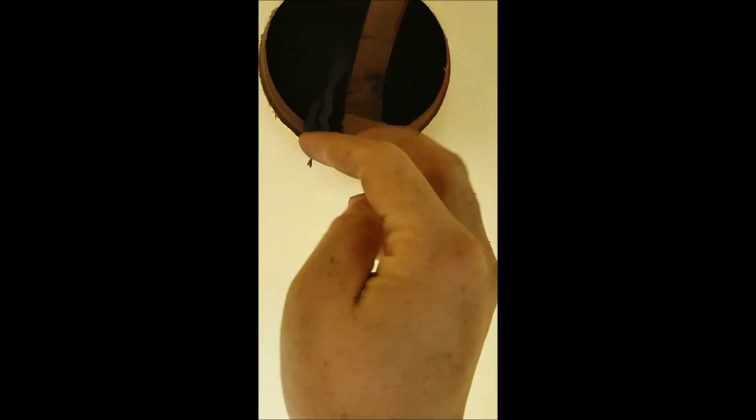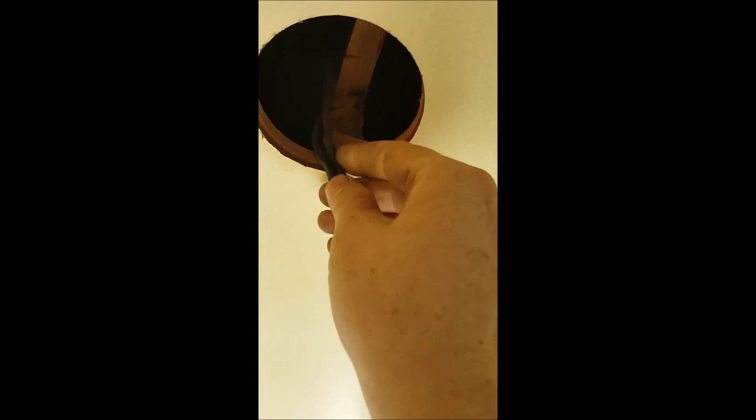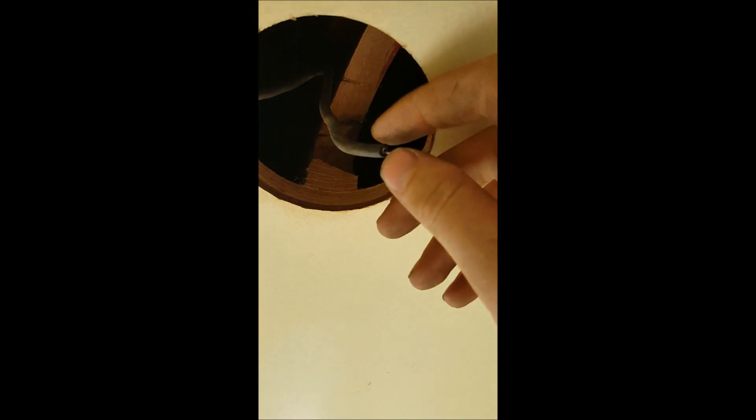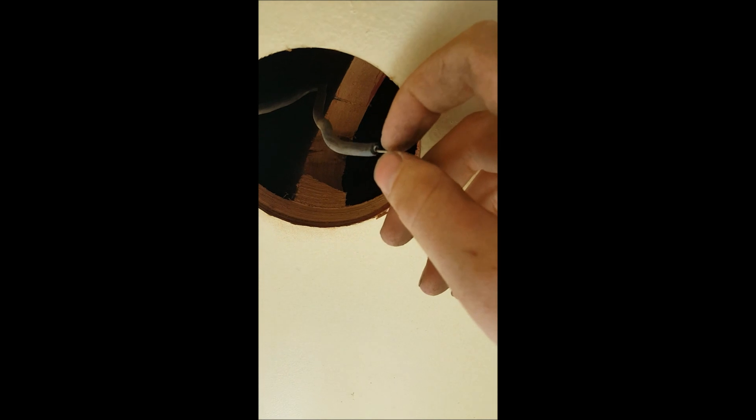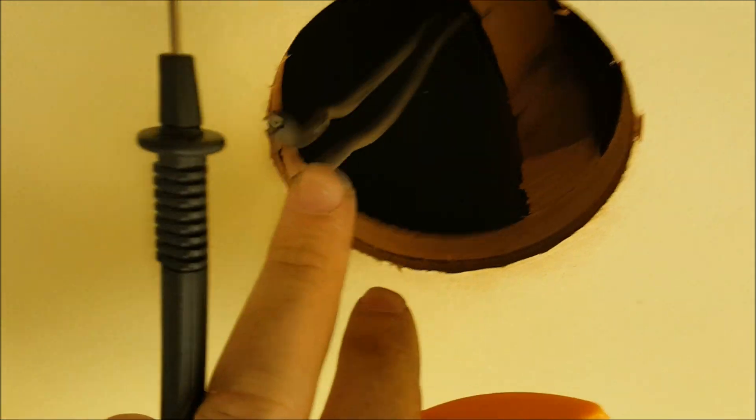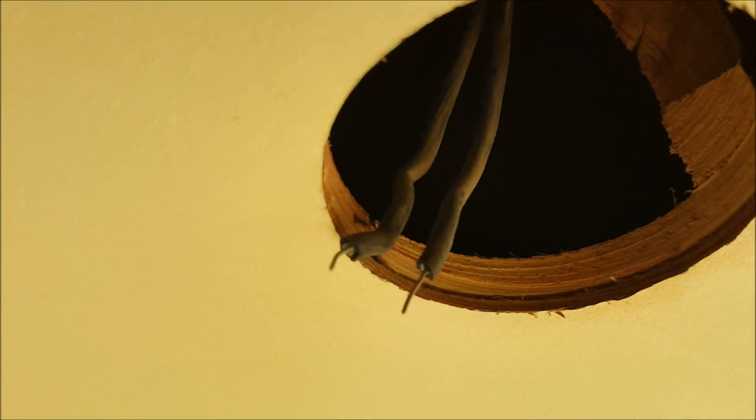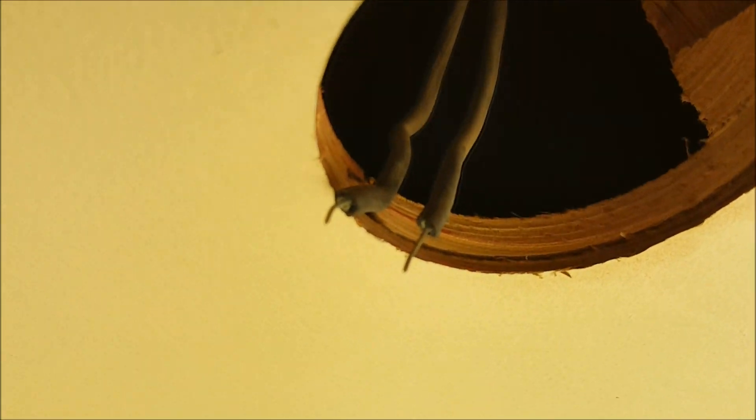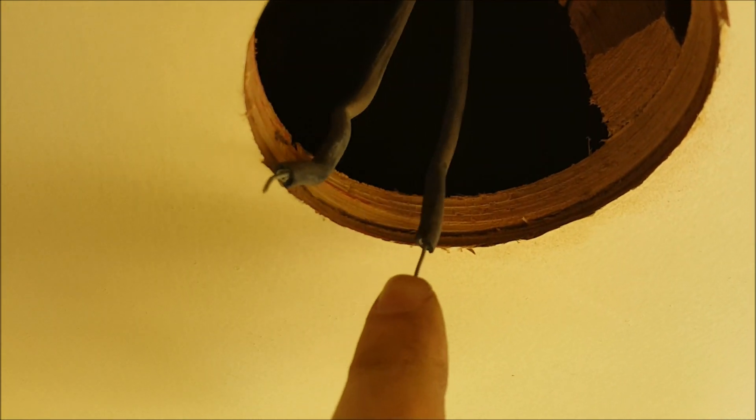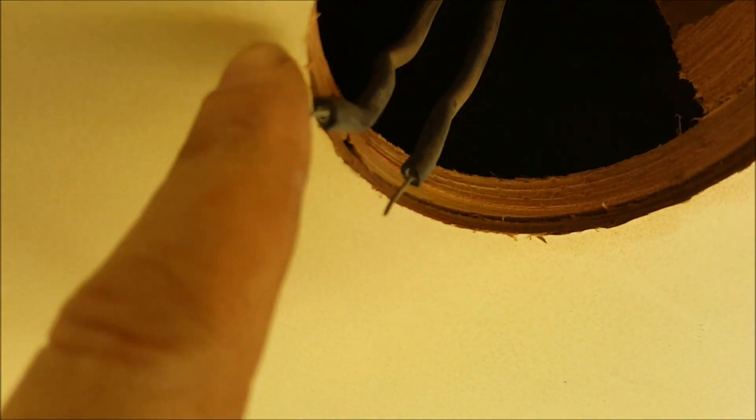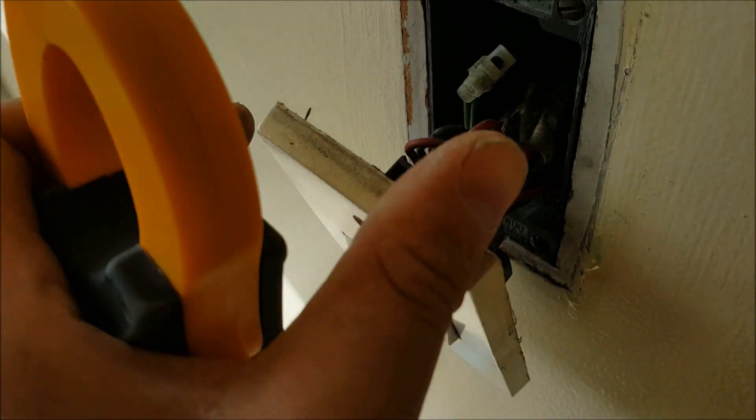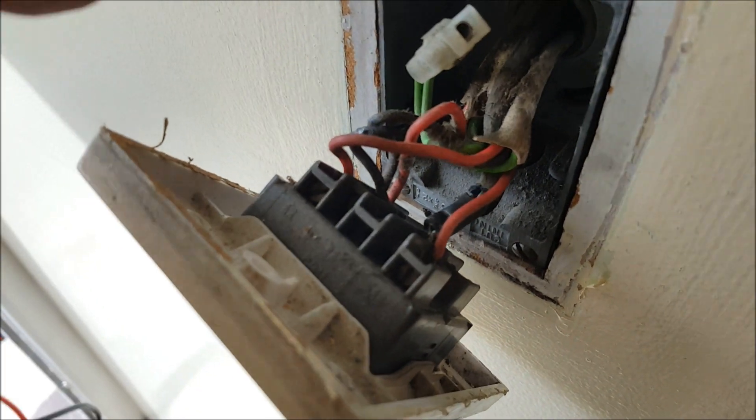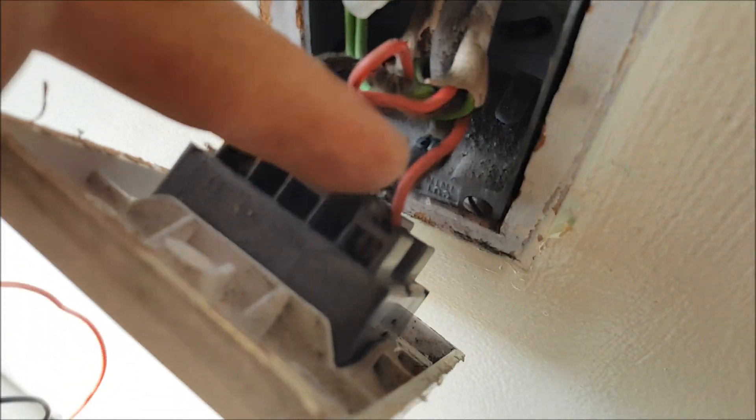Righto, so we've got our hole here ready for the downlight to go in. Next thing you want to do is grab down the old cable. Now I'm not going to be rewiring this rubber one. Further up it's in okay condition, so as long as we cut the bits off that have deteriorated over time and just use it from further up. With the rubber cable ends, we can't actually tell what end is phase and what's neutral up here because they're exactly the same inner colors. So what we'll do is go to the back of the switch.